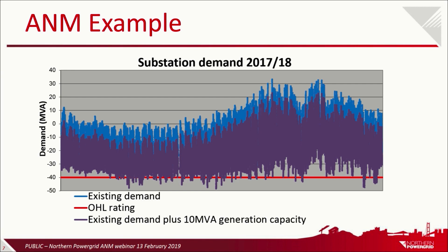If it was to join an ANM scheme, the ANM scheme itself would control that generator. It would look at the critical constraint location on the overhead line, run its analysis, and then issue a target set point to that generator to tell it how much it could actually export at any one particular time.